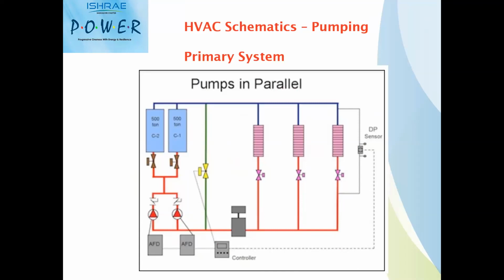All schemes have their own advantages as well as disadvantages, and it depends particularly on the schematic or the type of the building, and of course your installation costs, initial investment costs, as well as your operating costs. So the type of the schemes is basically decided based on your building design. And whenever it comes to selection of the pumps for particular applications, primary pumps will have to consider chiller pressure drops and piping pressure drops.